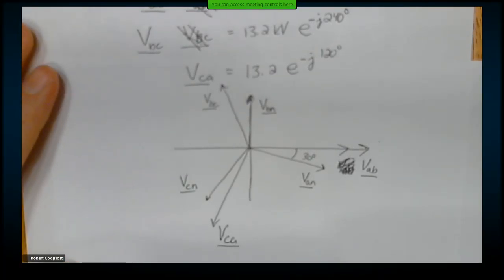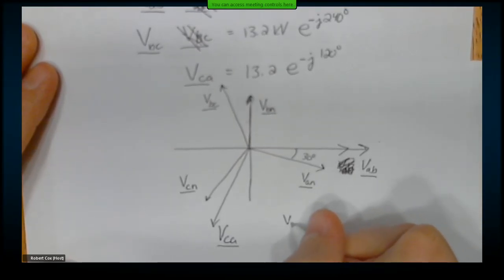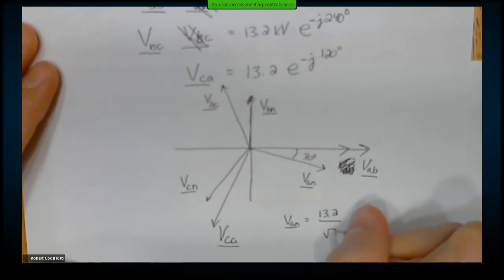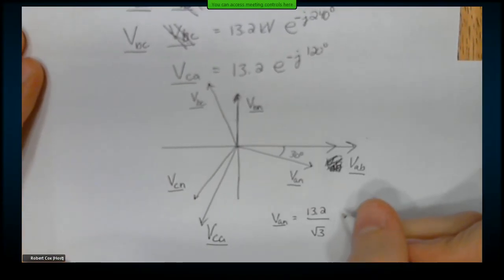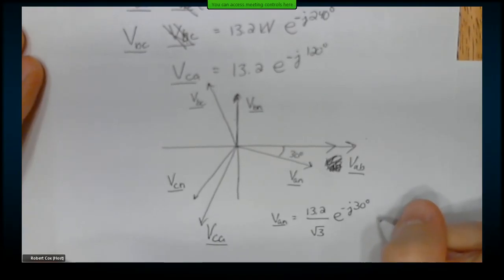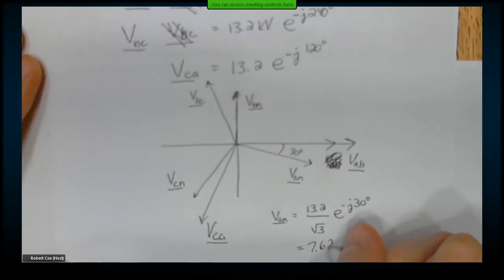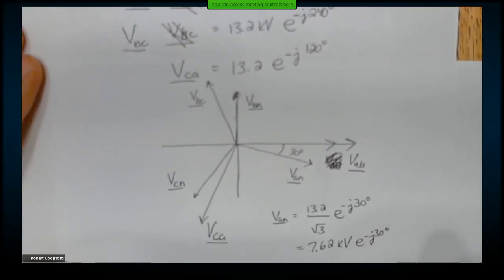So what does that tell us for each of those? Well, VAN is going to be 13.2 divided by the square root of 3, with an angle of negative 30 degrees. So calculating that: 13.2 divided by square root of 3 is 7.62 kV at negative 30 degrees.